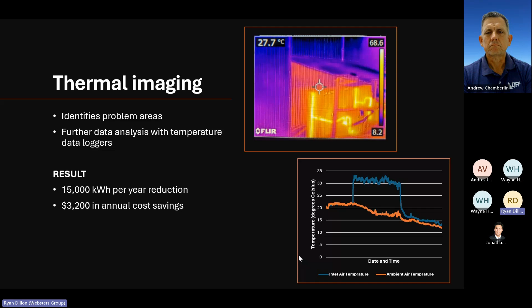And it's not only the amount of electricity that's consumed, it's also what we call the peak demand. Now, at this dairy site, we had a peak demand on the 15th of May of 120 plus kilowatts in that 30-minute period of which you get charged. So it's not only the area under the chart or the cumulative energy use, but also how spiky the chart is, where with Ergon or tariffs within other retailers and also across Australia, a move to cost-reflective pricing where you're charged for the peak demand is a constraint on growers and something they need to get their head around and develop solutions for.